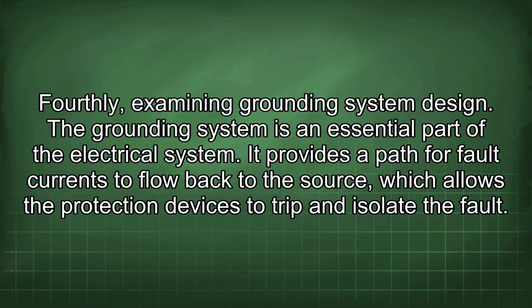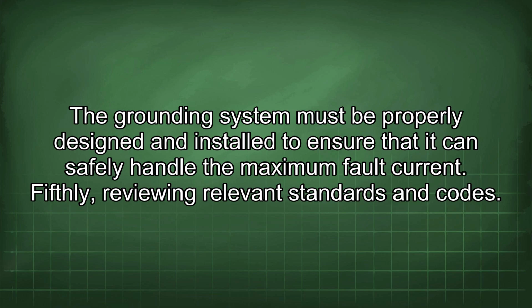Fourthly, examining grounding system design. The grounding system is an essential part of the electrical system. It provides a path for fault currents to flow back to the source, which allows the protection devices to trip and isolate the fault. The grounding system must be properly designed and installed to ensure that it can safely handle the maximum fault current. Fifthly, reviewing relevant standards and codes.